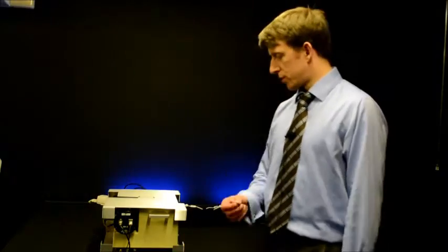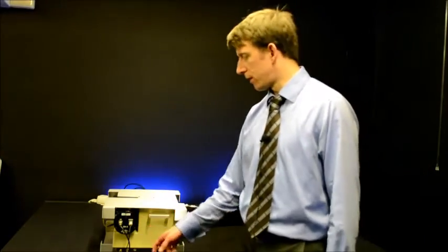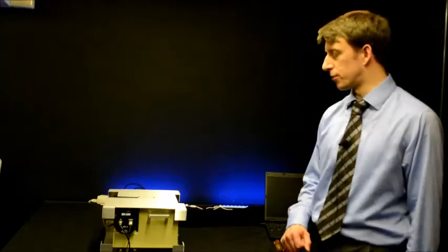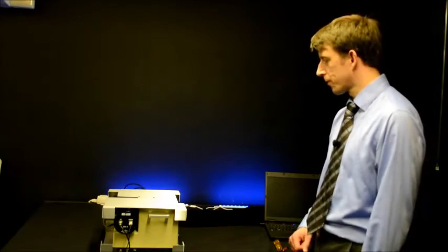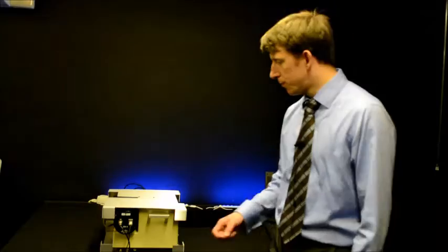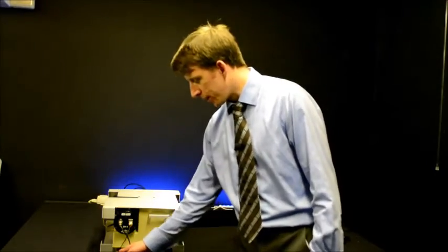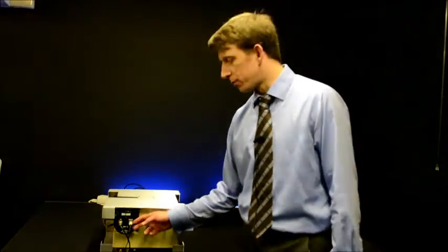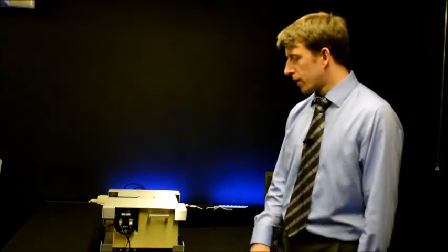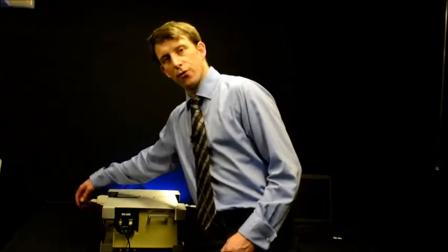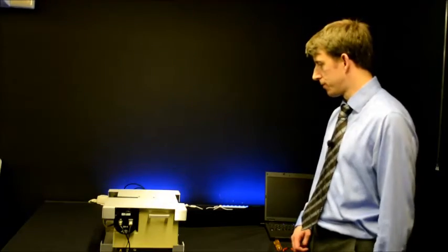To the base of the unit is provided a transimpedance amplifier with 2 inputs, which detects the signal from the photomultiplier and provides a reading to the computer through an A to D converter. When used in radiometer mode, one must remove the cable connecting the signal of the photomultiplier to input 1, and one will use input 1 for the reference diode or the device under test through the 472 unit, and input 2 for the monitor photodiode.